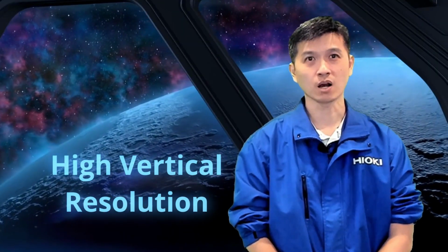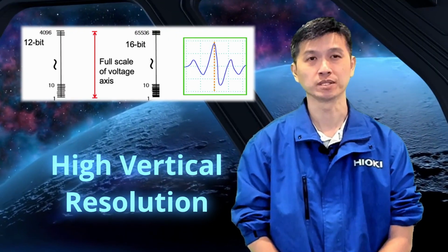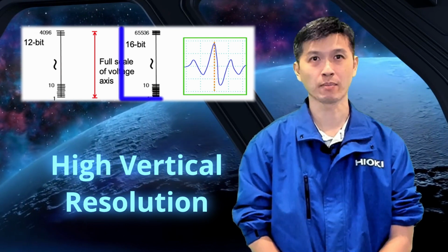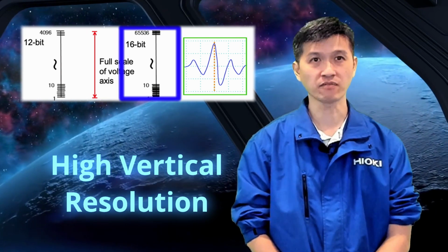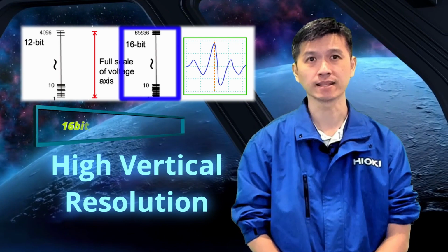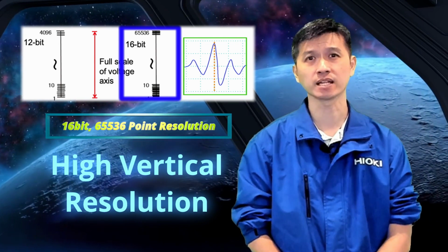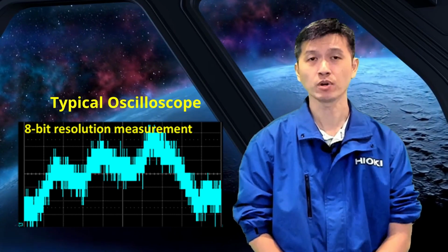When it comes to resolution, I would like to refer to this as vertical resolution. The higher the vertical resolution, the better the sensitivity of measurement. Therefore, having a 16-bit resolution means there are 65,536 points of resolution. For a typical oscilloscope, the resolution is only up to 8 bits.